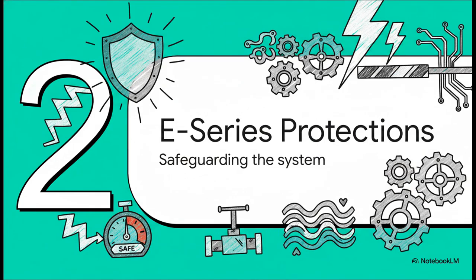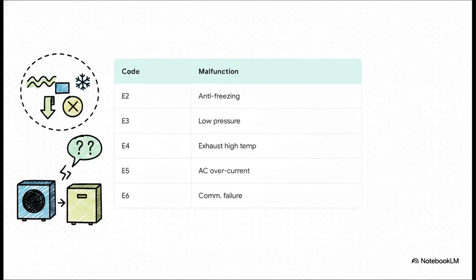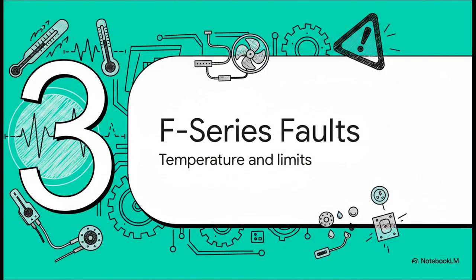Section 2. E-Series system protections. Safeguarding against pressure and current anomalies. Think of the E-Series codes as the primary defense shields for your unit's overall operation and power management. Looking at the most common issues here, we can see a clear pattern. If you see an E3, your system detects a block or low pressure in the refrigerant. E5 points to overcurrent protection. And E6? That's a super common one, a simple communication failure. It's essentially your system saying, hey, the inside wall unit and the outside box aren't talking to each other right now.